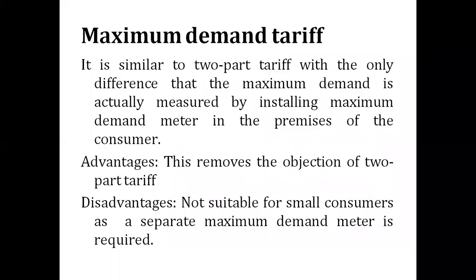Let's start with the Maximum Demand Tariff. The Maximum Demand Tariff is similar to the Two-Part Tariff with one difference: the maximum demand is actually measured by installing a Maximum Demand Meter in the premises of the consumer. In the Two-Part Tariff, one charge is based on maximum demand, but consumers had to pay for a declared maximum demand even if they did not reach it.